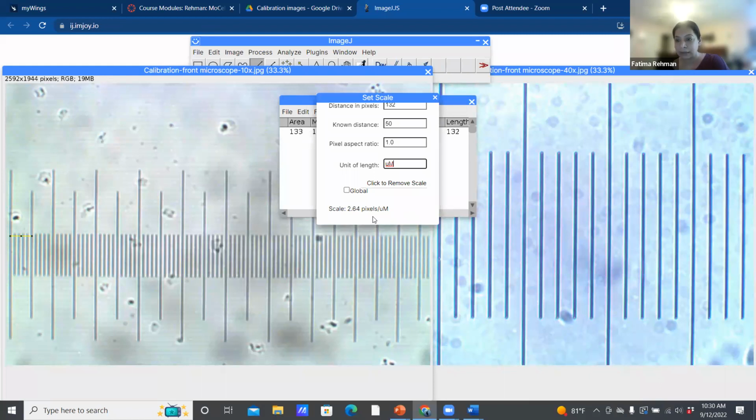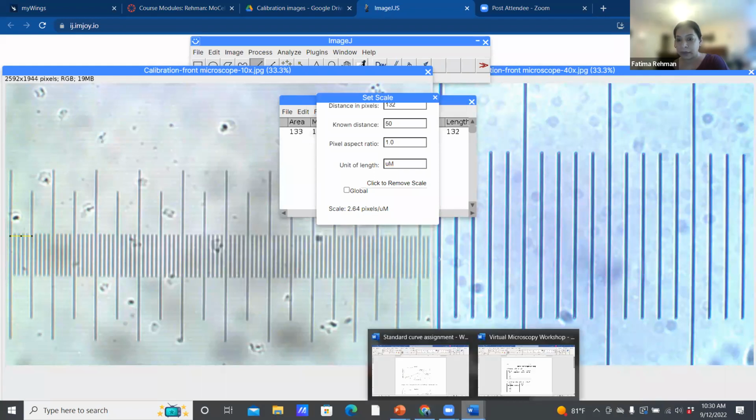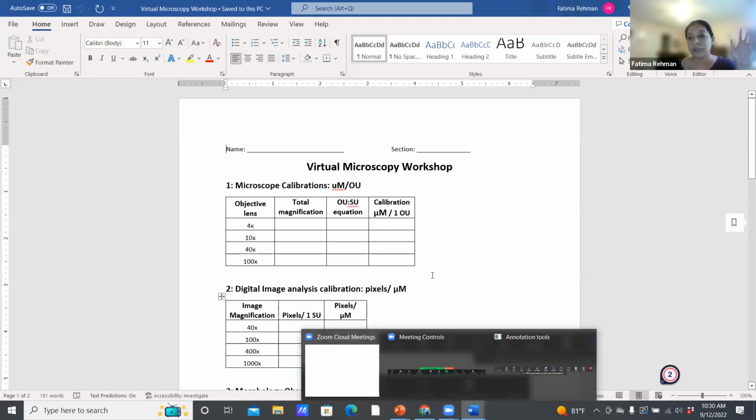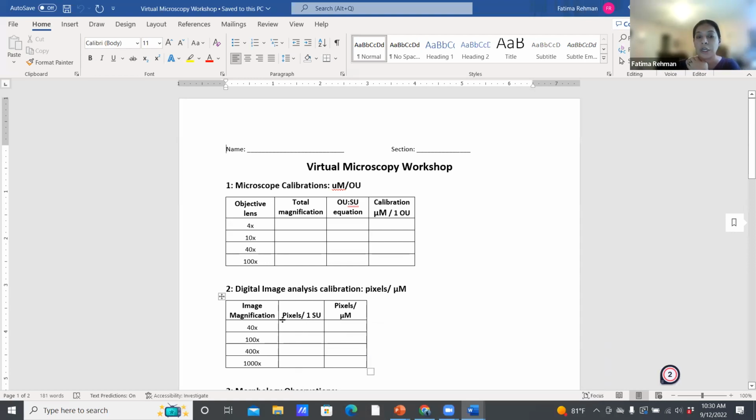You guys got that? So when you look at this, it's telling you to do the same thing for all of those. So you're going to write those pixels per stage unit and then pixels per micrometer. And that's how you're going to do that. So you do need all 4 images.